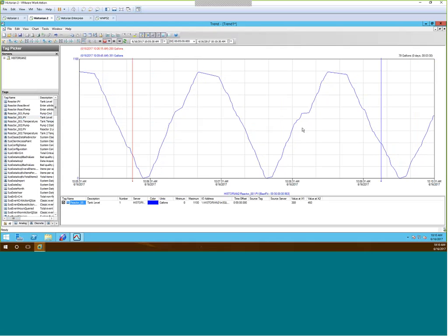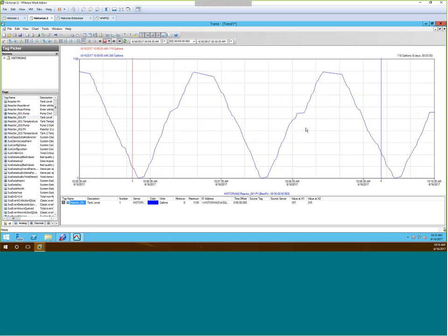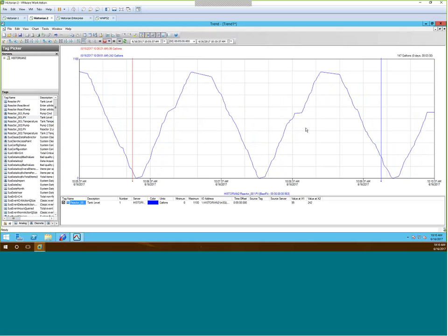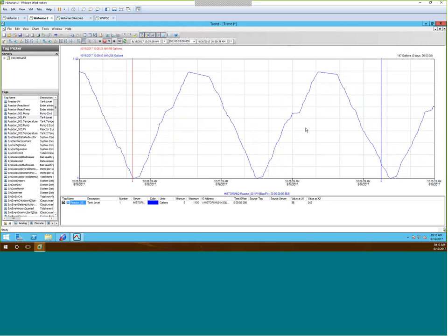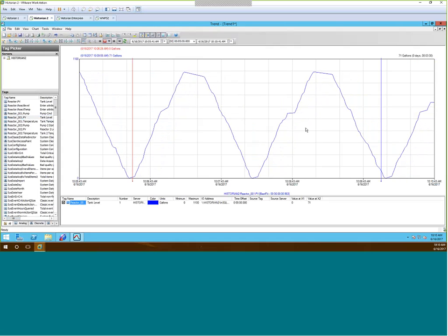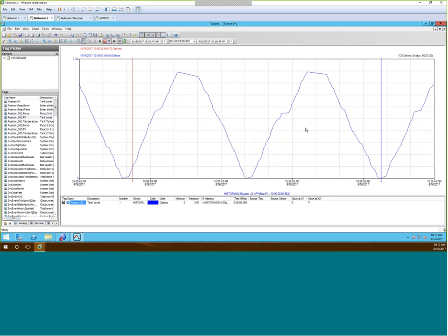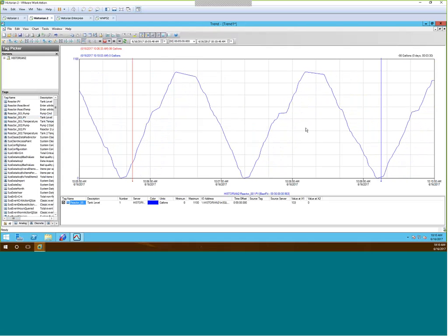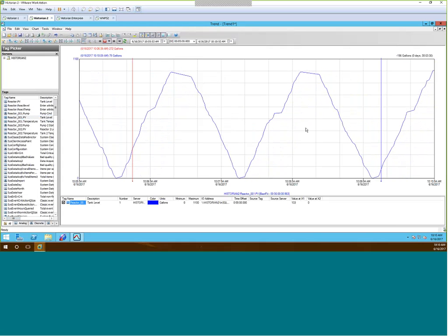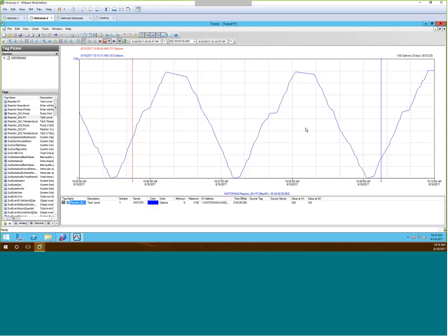So as you can see, setting up a partner historian is very simple. Now, the one thing that I do want to clarify with partner historian is that both of these historians are running at the same time. They're not on a standby phase. They're always active. So you will have 2 historians running constantly, and then the app server engine would send data to both historians at the same time. So if one goes down, you have instantly right away the same exact data on the secondary historian.